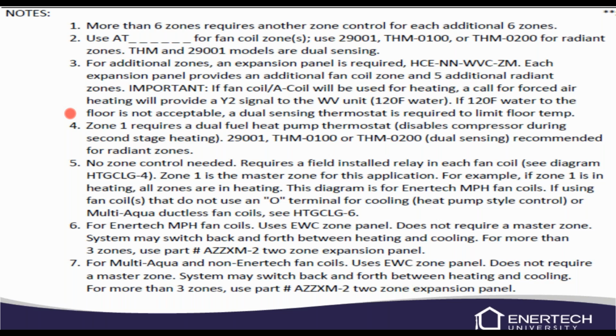Because a lot of times we need to limit the heat that's going to that floor. There could be sensitive hardwood floors or something like that. So anytime we've got radiant and forced air, we're going to want to use dual sensing thermostats. If you need additional zones, again, the expansion panel is required. Each expansion panel provides a fan coil and 5 radiant zones.